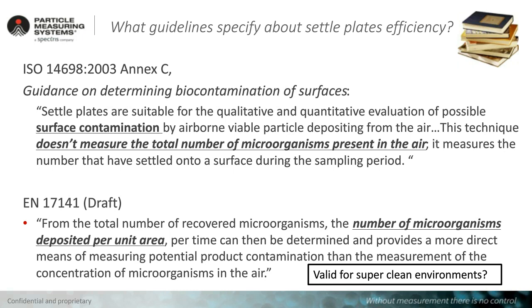That's true. But is that really true, and is it really valid for a super clean environment with high turbulences? We just learned that especially when we have high airspeed, there is a cleaning effect from the airspeed that will, in the end, remove these MCPs from the air and will prevent them from settling.